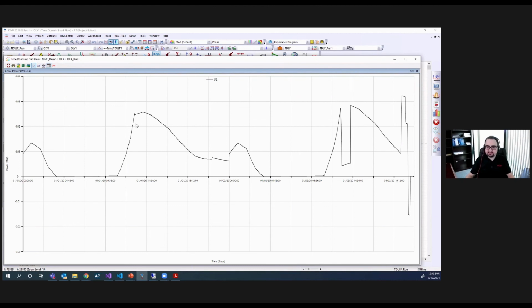And then once we have peak time, during the peak time, once we are importing power from the utility, the Microgrid controller will dispatch the battery to start discharging. As a result, it will reduce the import power from the utility, and it will reduce the cost of operation.